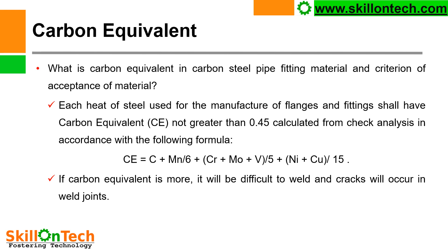By this formula we can calculate the carbon equivalent. If the carbon equivalent is more, it will be difficult to weld and cracks will occur in the weld joints. Therefore, carbon equivalent is a very important criteria in carbon steel pipelines, and suitable pipelines shall be procured considering carbon equivalent.